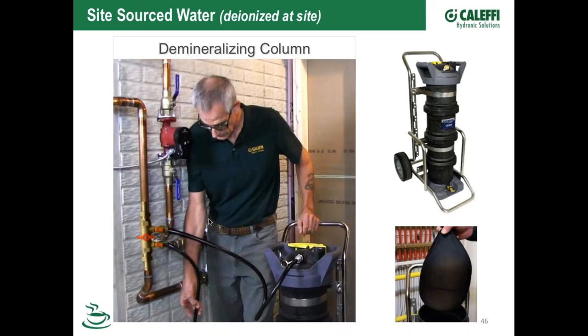But with the conductivity down, as well as the pH being somewhat lowered, any metals in the system are going to end up reacting with the water. What happens in any hydronic system is your pH will tend to drift back up, and it typically stabilizes somewhere around 8, a range that just about every boiler manufacturer, whether stainless steel or aluminum, is happy with.